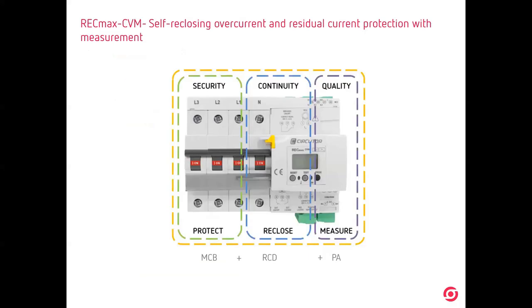Also, you have one direct device, up to 63 amps, an MCB called a RECmax-CVM. This is a self-reclosing overcurrent and residual current protection relay with measurement. So what does it mean? We have a compact device, which is an MCB, so we are tripping by overcurrent or short circuit. We also have an RCD, residual current device. We are measuring the leakage, so we need a transformer, obviously a toroidal. We will measure the leakage, and if there is a leakage, this will trip automatically.